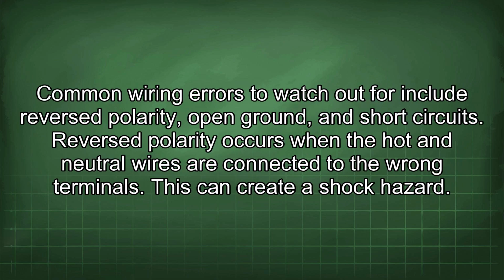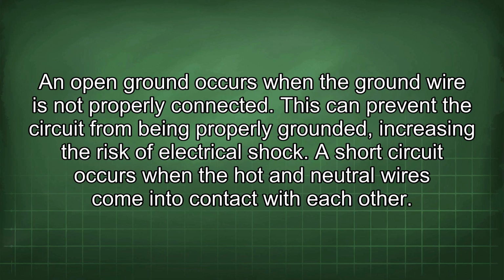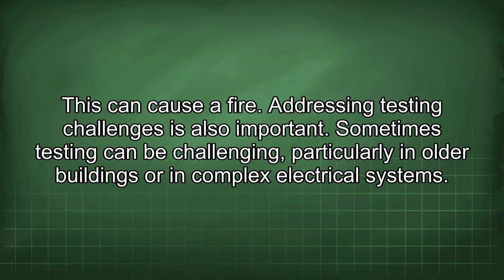Common wiring errors to watch out for include reverse polarity, open ground, and short circuits. Reverse polarity occurs when the hot and neutral wires are connected to the wrong terminals. This can create a shock hazard. An open ground occurs when the ground wire is not properly connected. This can prevent the circuit from being properly grounded, increasing the risk of electrical shock. A short circuit occurs when the hot and neutral wires come into contact with each other. This can cause a fire.